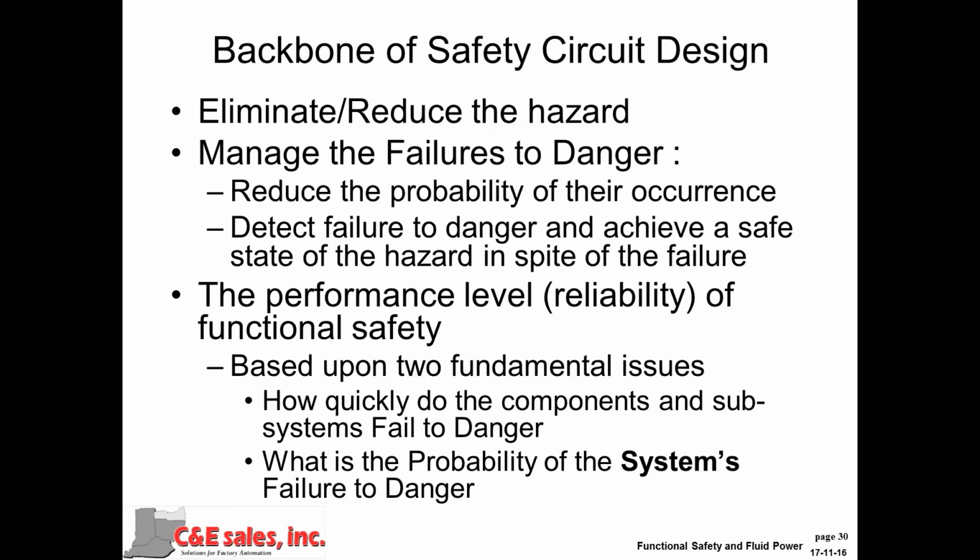Okay, so the backbone of safety circuit design is primarily to eliminate or reduce the risk. To do that with safety control systems, we have to manage the failures to danger. I will keep saying failures to danger because some failures I can accept because they do not lead to an increase in risk, whereas other failures do.